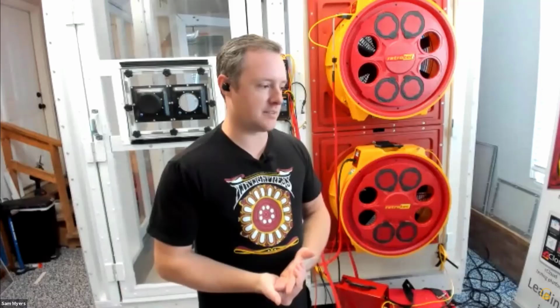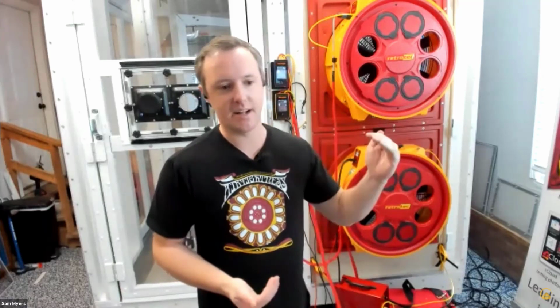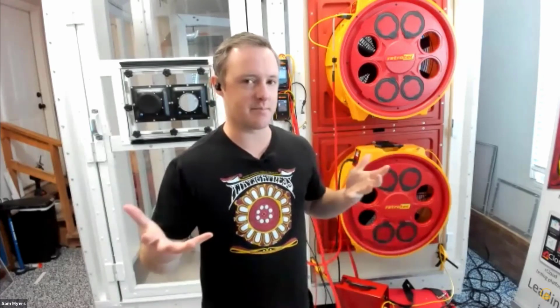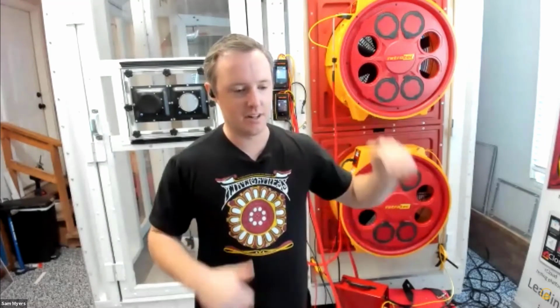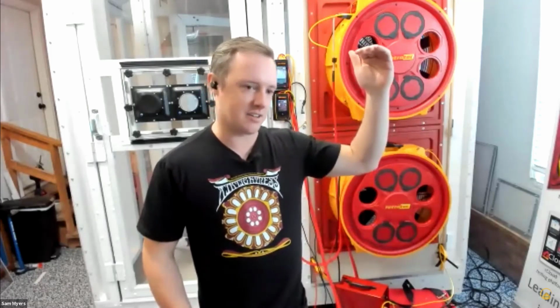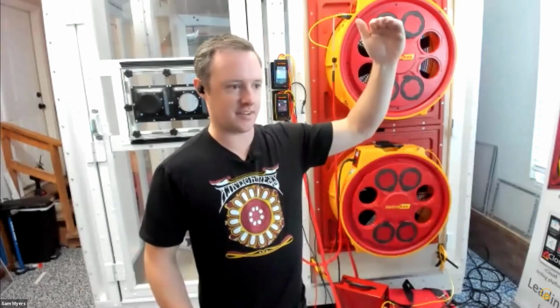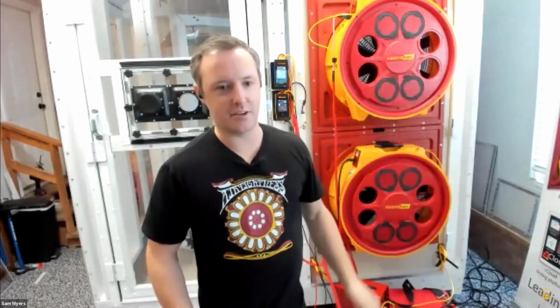So usually what you want is a retention time at a certain height for 10 minutes. Retention time means whenever that fire suppression comes out, you want it to stay at a certain level. So say your servers are 6 feet tall, you want a 6-foot retention at 10 minutes. You have to know what type of fire suppression you're using.